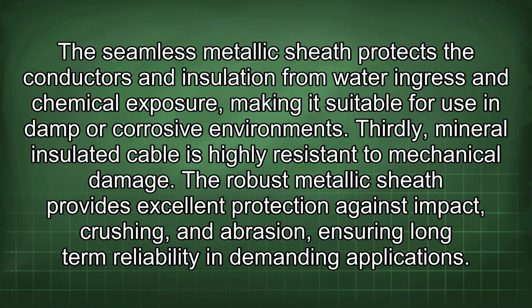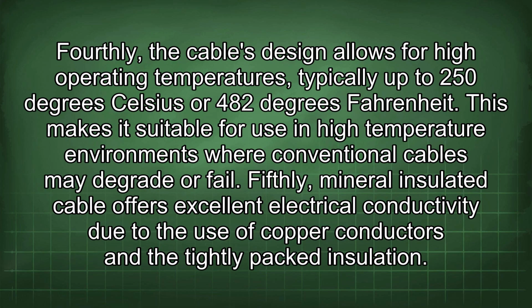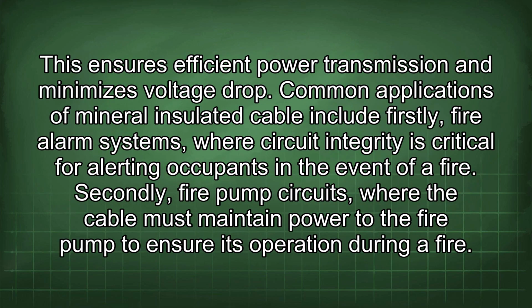Thirdly, mineral-insulated cable is highly resistant to mechanical damage. The robust metallic sheath provides excellent protection against impact, crushing, and abrasion, ensuring long-term reliability in demanding applications. Fourthly, the cable's design allows for high operating temperatures, typically up to 250 degrees Celsius or 482 degrees Fahrenheit. This makes it suitable for use in high-temperature environments where conventional cables may degrade or fail. Fifthly, mineral-insulated cable offers excellent electrical conductivity due to the use of copper conductors and the tightly packed insulation. This ensures efficient power transmission and minimizes voltage drop.